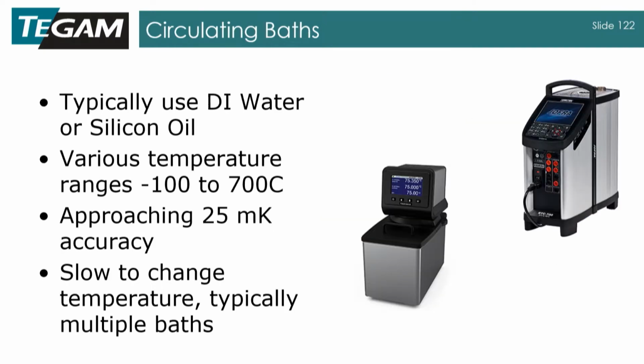When you want to get more accuracy, then you go to a circulating bath. The way a lot of people use circulating baths, they use DI water or silicon oil. You can get various temperature ranges from -100 to 700 C. Obviously, this is not water, and neither is this. This is a high temperature oil, because the water's going to freeze there. And you can find some baths that'll control to within 25 milliKelvin.